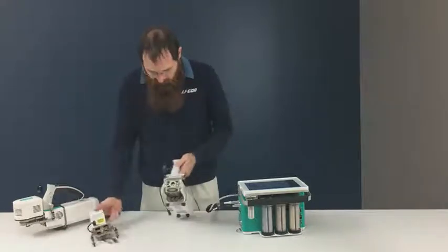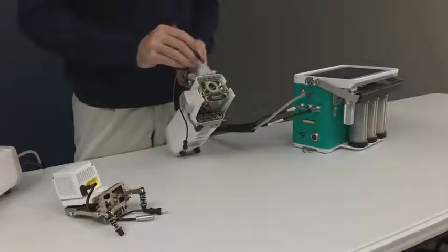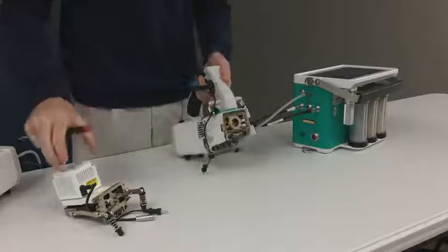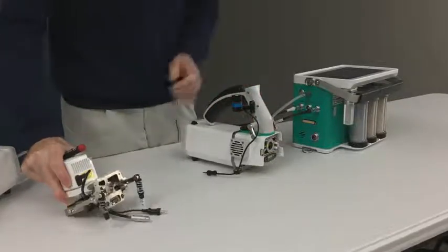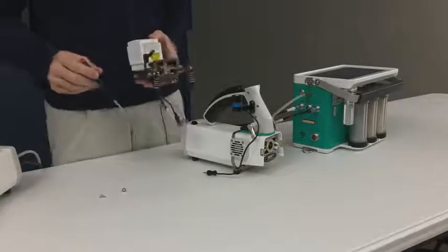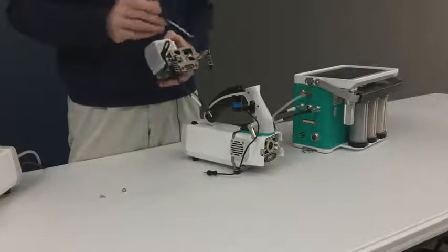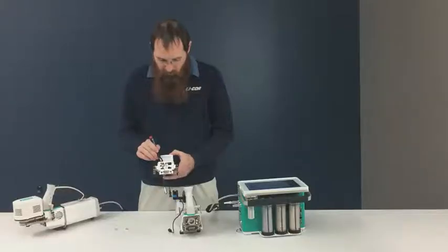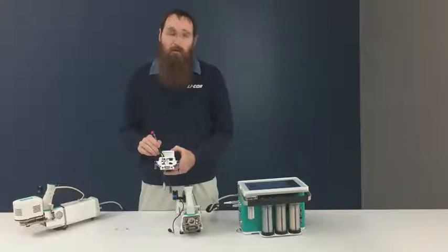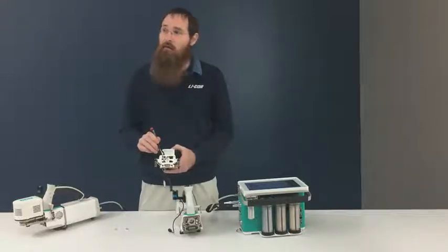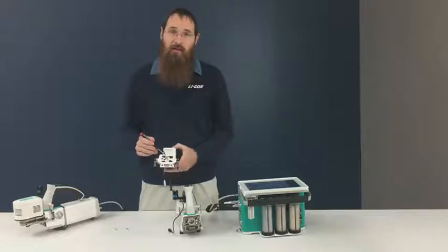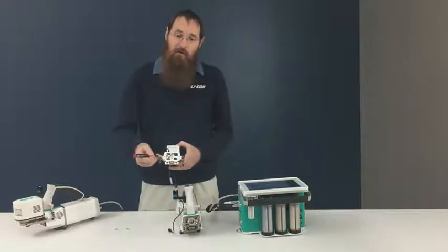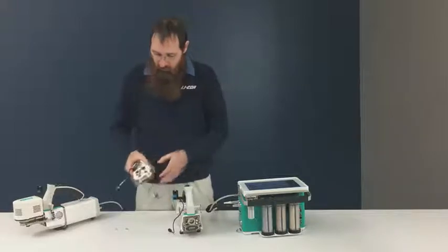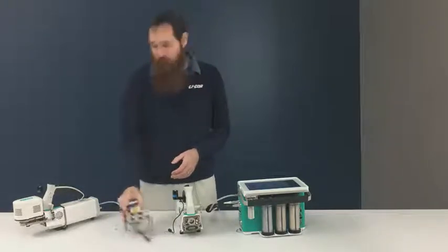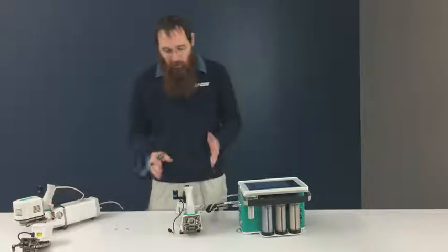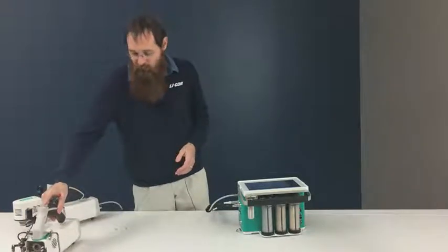When the chamber comes off, you have access - you can see the mixing fan and a couple of filters. I'll show you where these are in the flow path later. But the real reason I'm taking this off is to show you there are no O-rings, and to show this little connector. There's a small computer chip here that holds identifying information about the chamber, along with calibration information associated with the accessory. When I plug this into an instrument and turn it on, the instrument knows what chamber is there, and changes its configuration automatically without the user having to do anything.